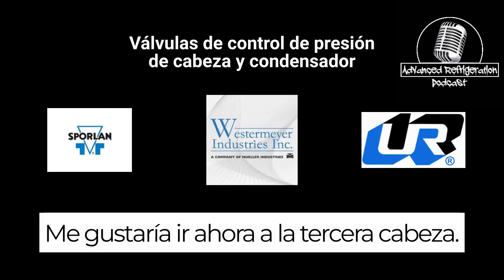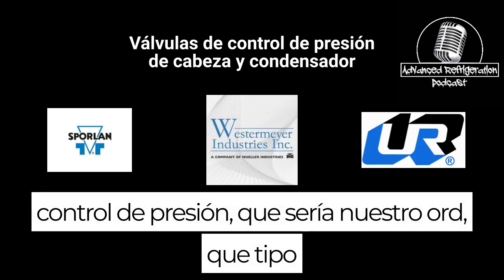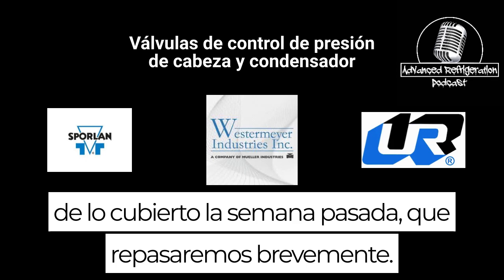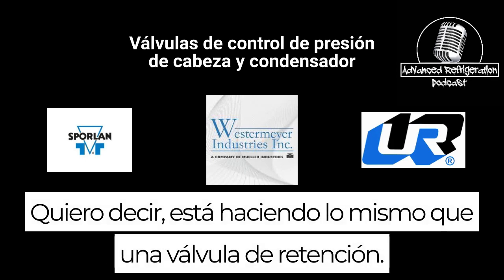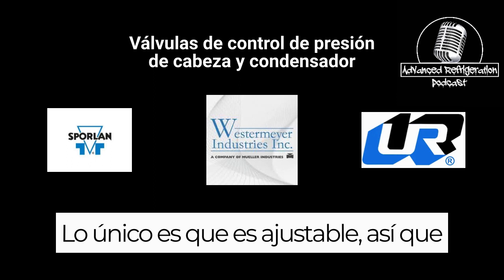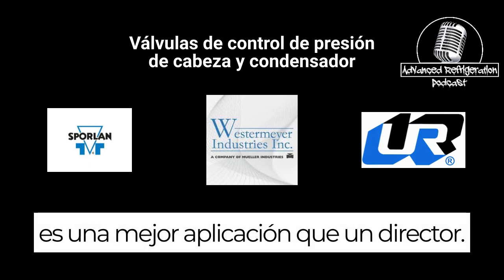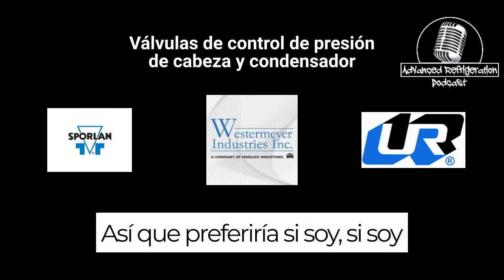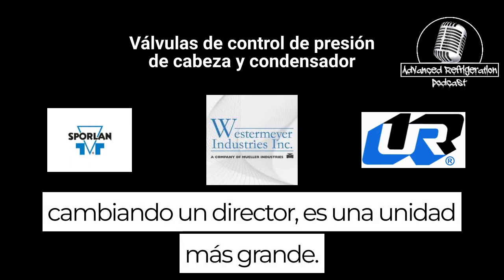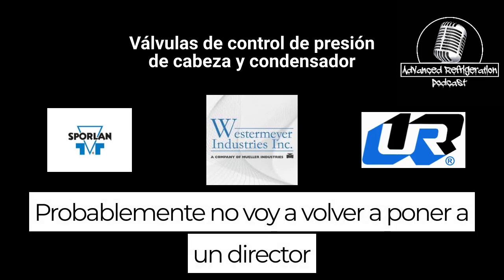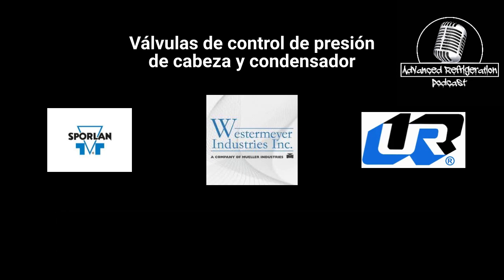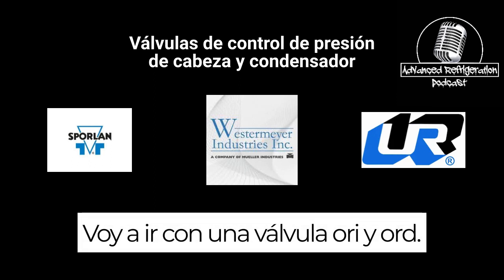I would like to go into now the third head pressure control, which would be our ORI and our ORD, which we kind of covered last week, which we'll just go over briefly. I mean, it's doing the same thing as a holdback valve. The only thing is it's adjustable. So it's a better application than a headmaster. If I'm changing a headmaster out of a larger unit, I'm probably not going to put a headmaster back. I'm going to go with an ORI and an ORD valve.